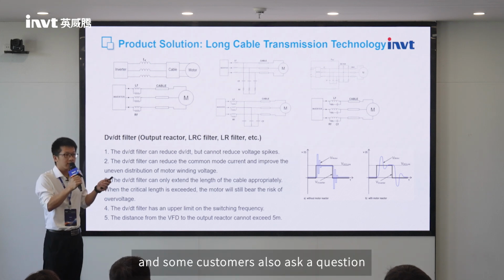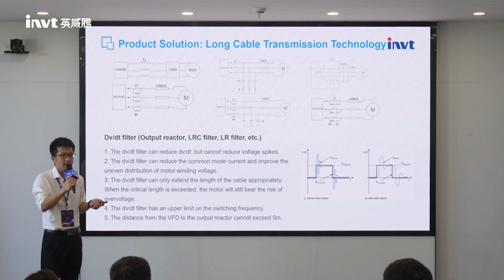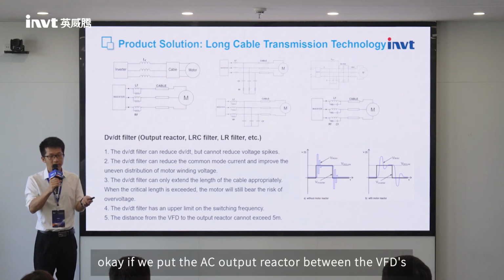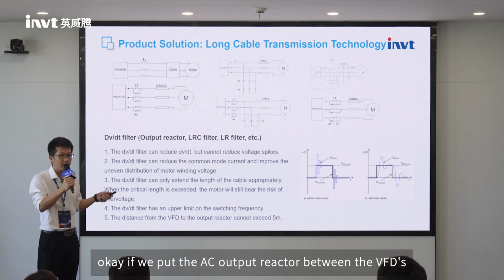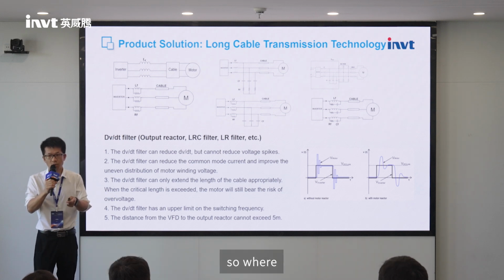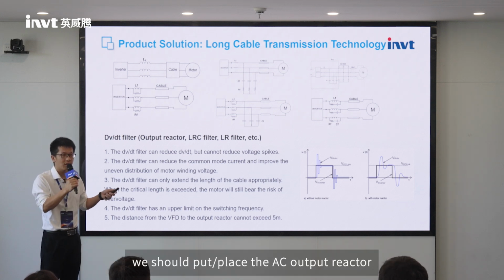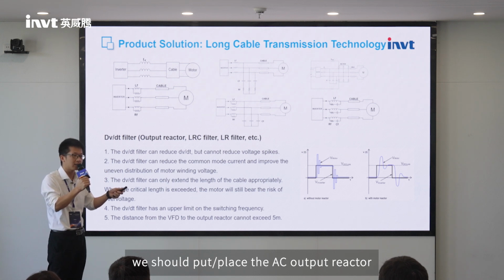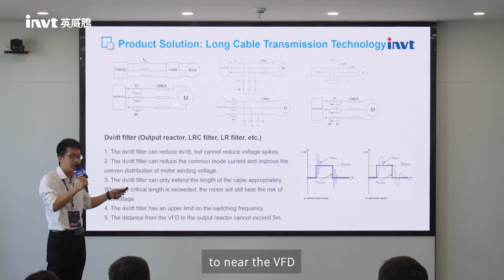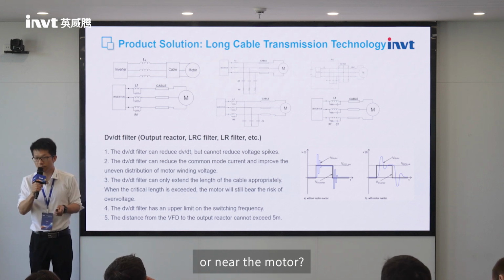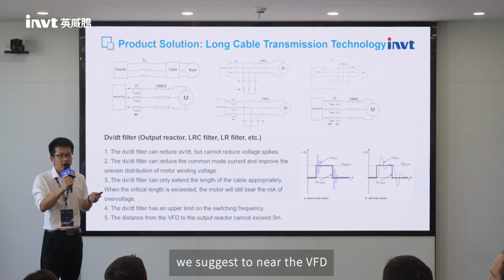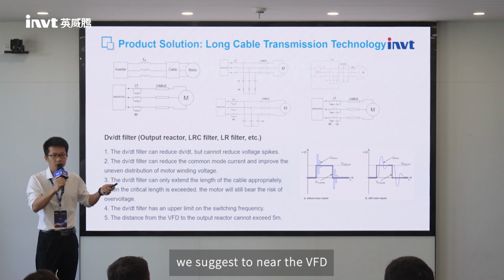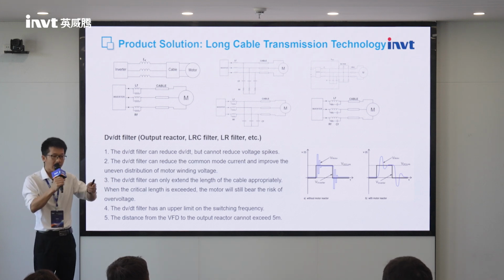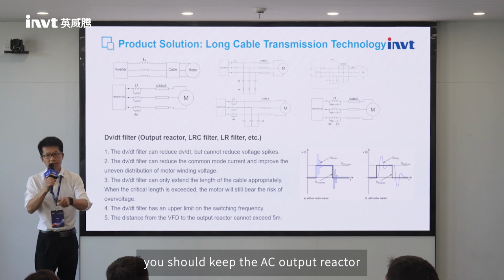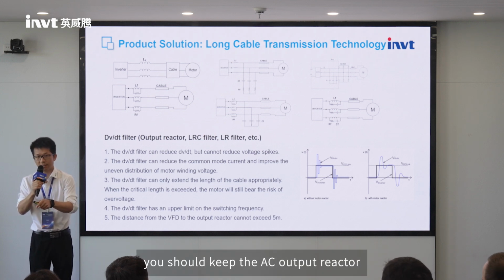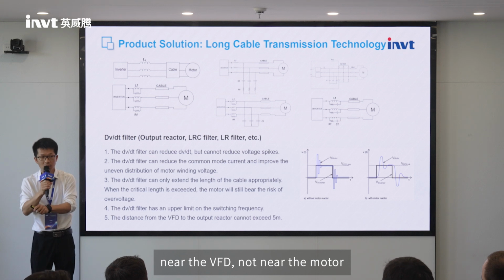Some customers also ask: if we put the AC output reactor between the VFD output and the motor, where should we position it? Near the VFD or near the motor? Normally we suggest placing it near the VFD, no more than 5 meters away, not near the motor.